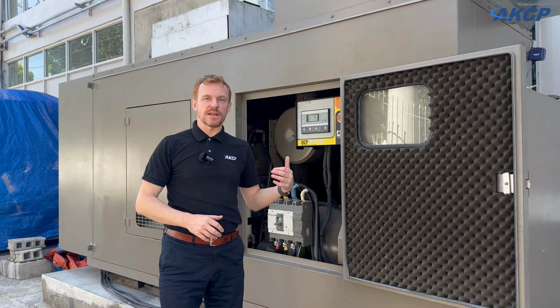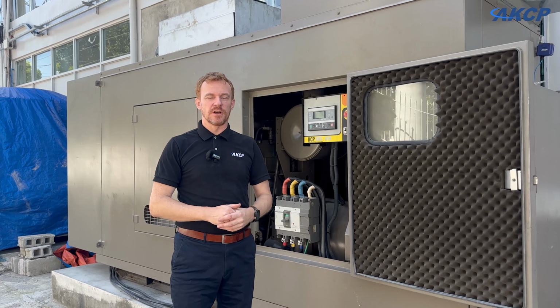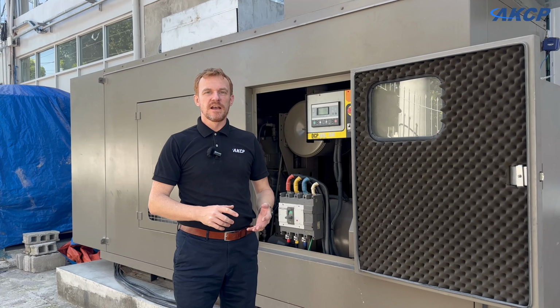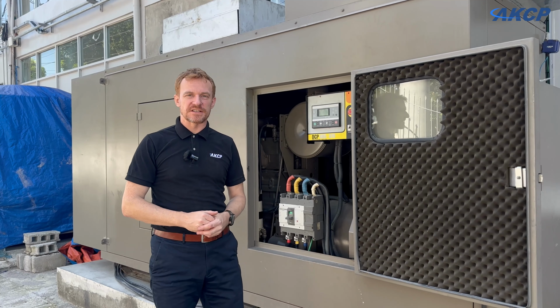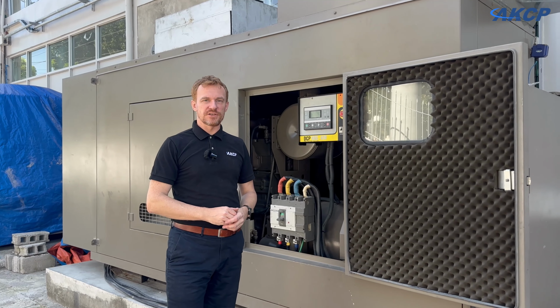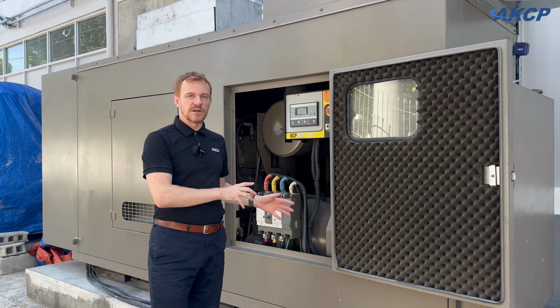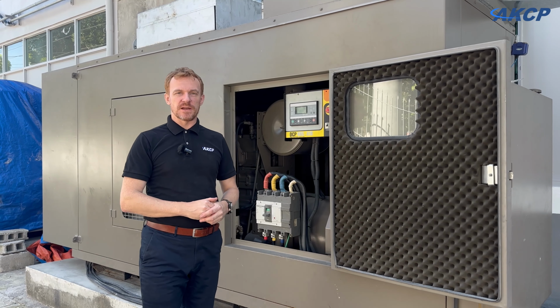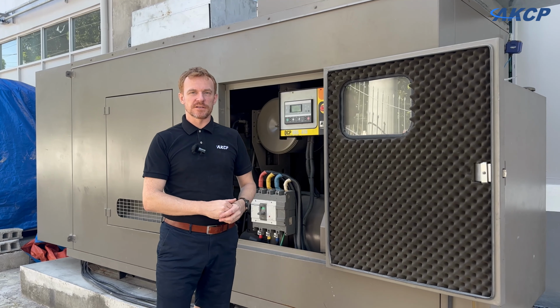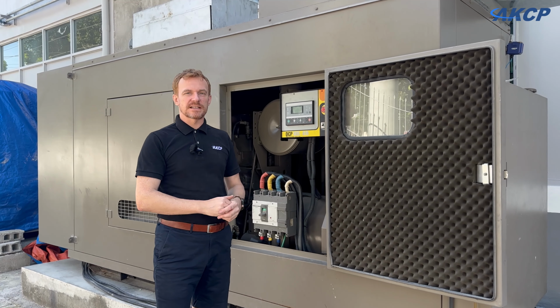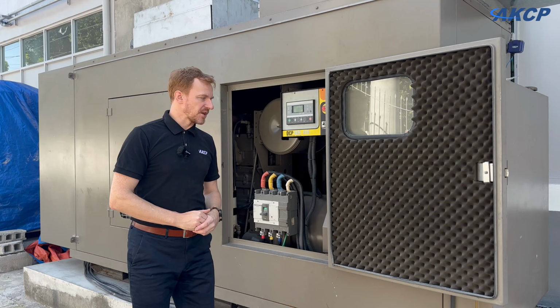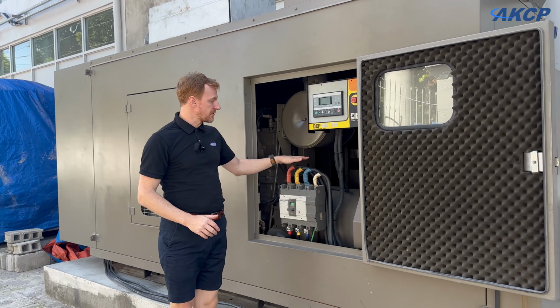Every week we test the generator just to make sure that it runs. It's not good for the engines to sit for too long without being operational, so weekly we turn it on and run it for 15-20 minutes. That circulates the lubricants and makes sure it's kept in good condition, and also helps maintain the battery.